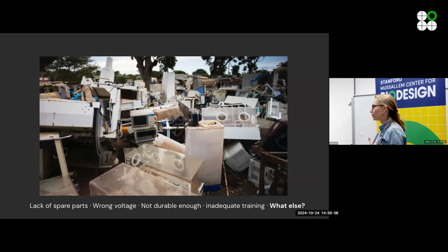There's often a lot of turnover, depending on the hospital. So, you know, it just might not get used. The other reason why these are here is because spare parts are often cannibalized because it is really hard to get spare parts. And so, if something needs to be fixed, an engineer at the hospital might say, hang on, and run into the back and see if they have a device that they can grab a sensor off of or something else that's in use.